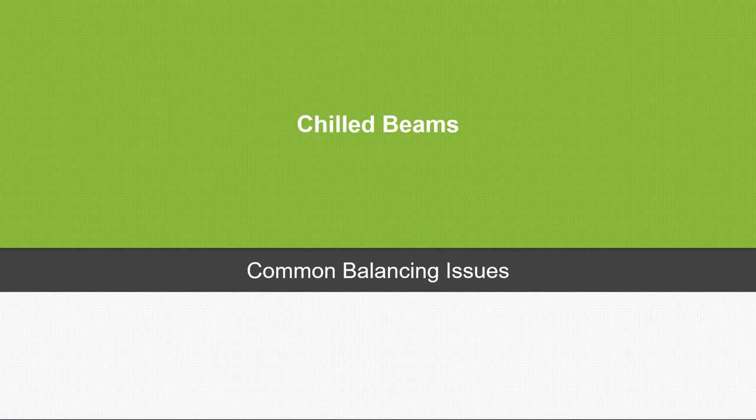This is Ed. I do want to point out regarding flow regulators, there should be a level of caution when using a flow regulator. Make sure you look at what the error is on the flow regulator. A lot of flow regulators out there are either plus or minus 5 or plus or minus 10% of the total flow of the size of the regulator you're using. So if you've got 50 or 60 CFM on a primary air and you have a 10% error rate associated to that, that could be pretty significant.